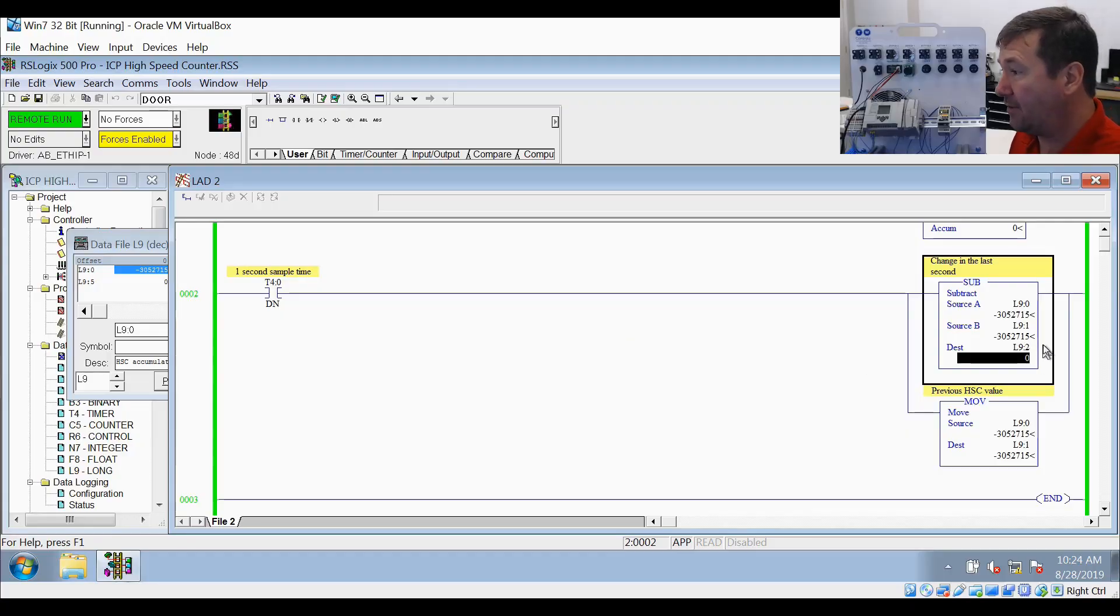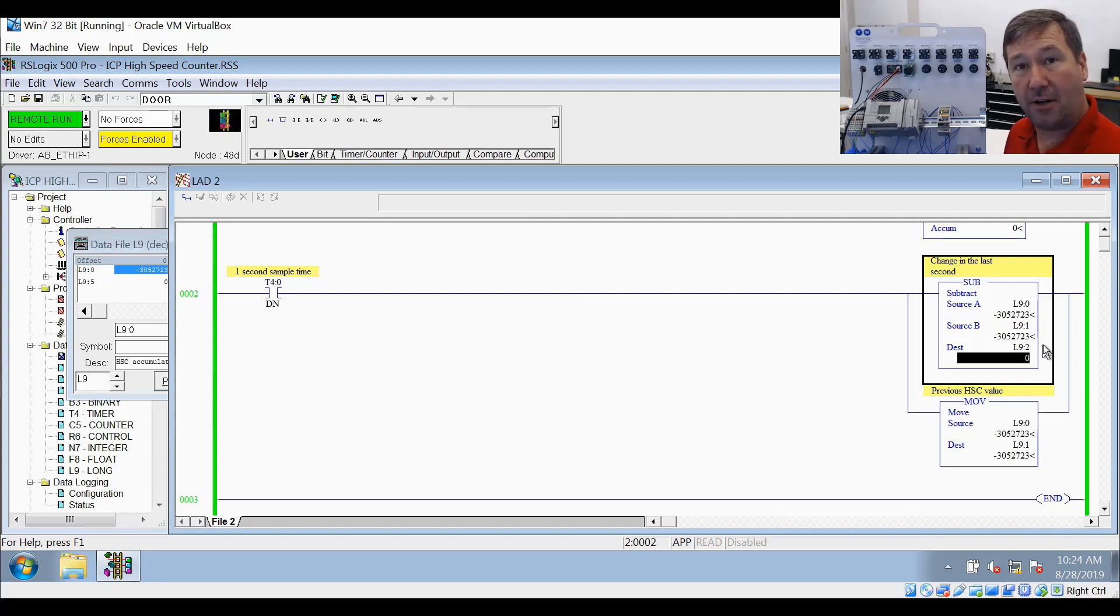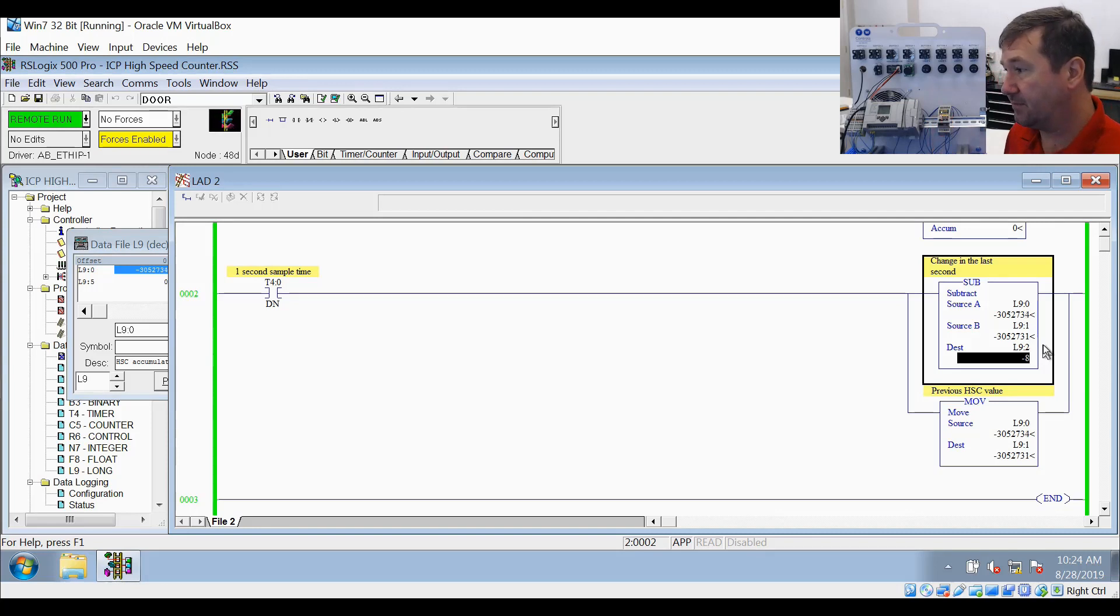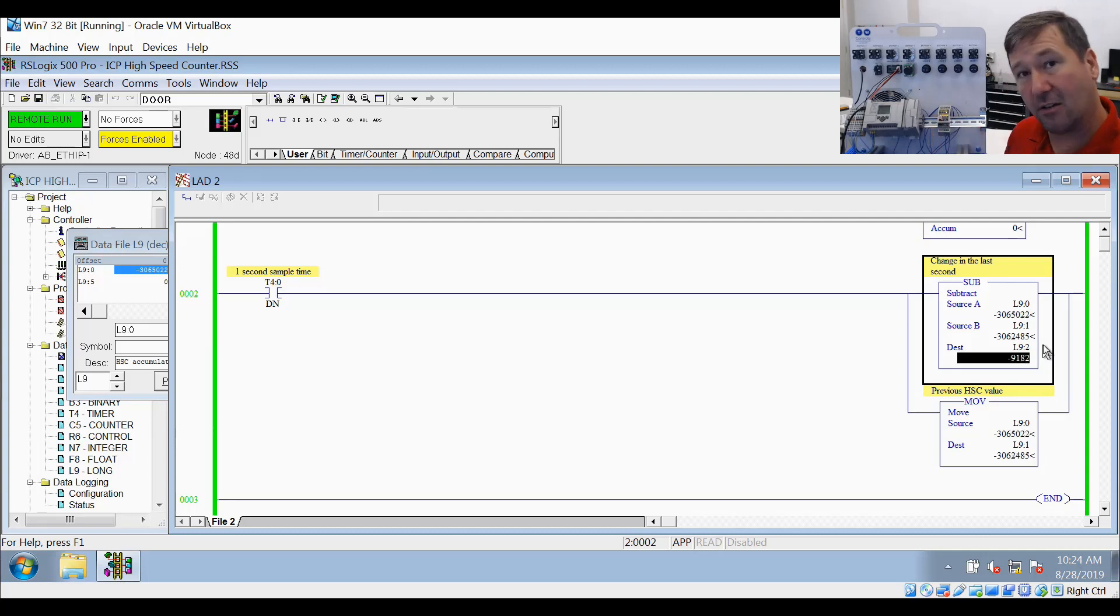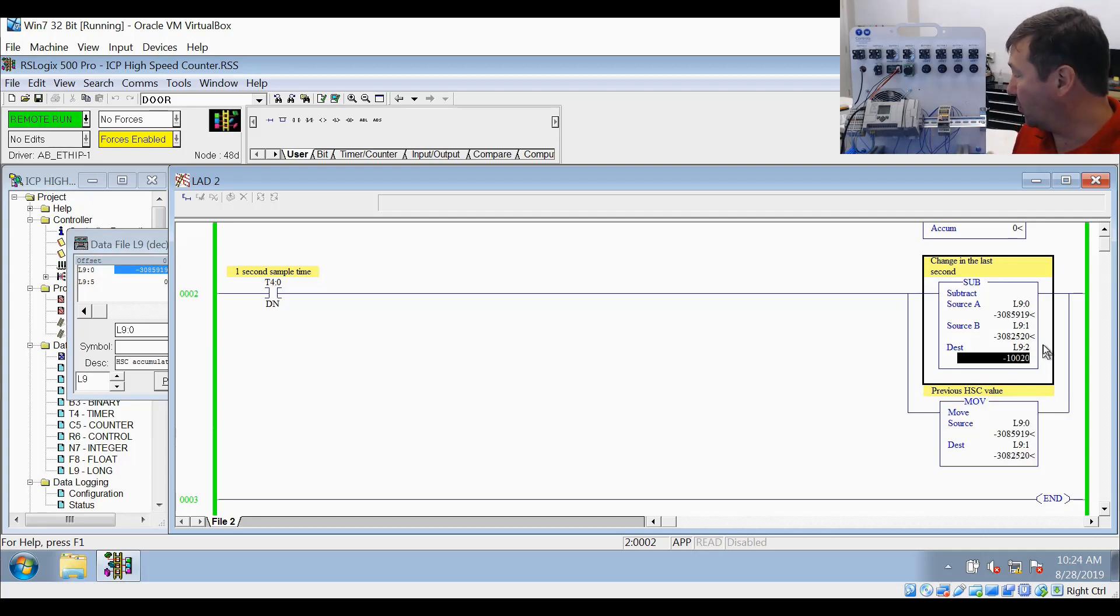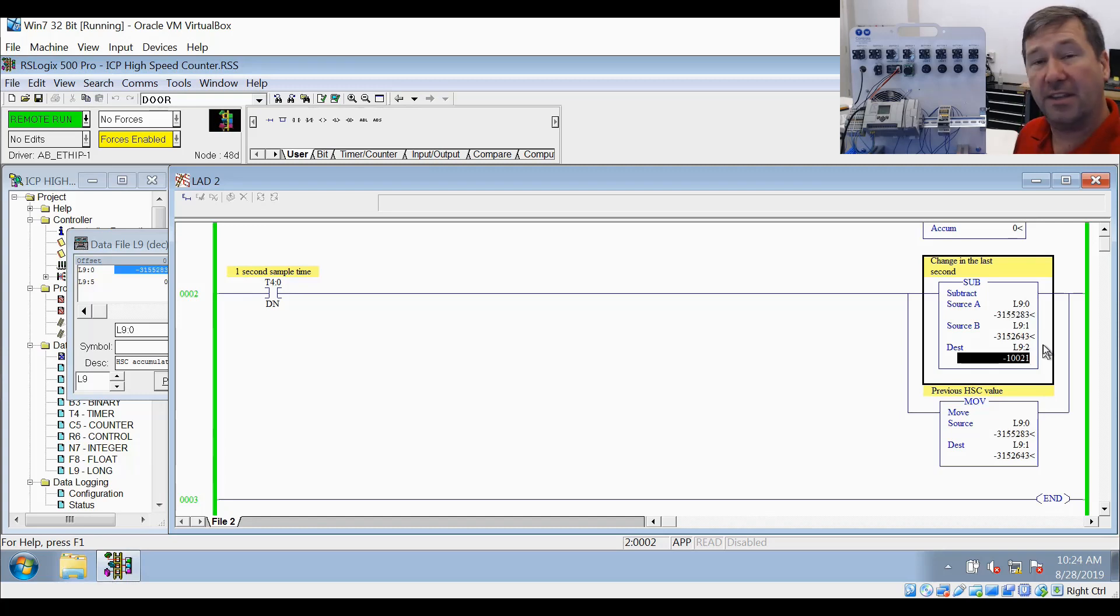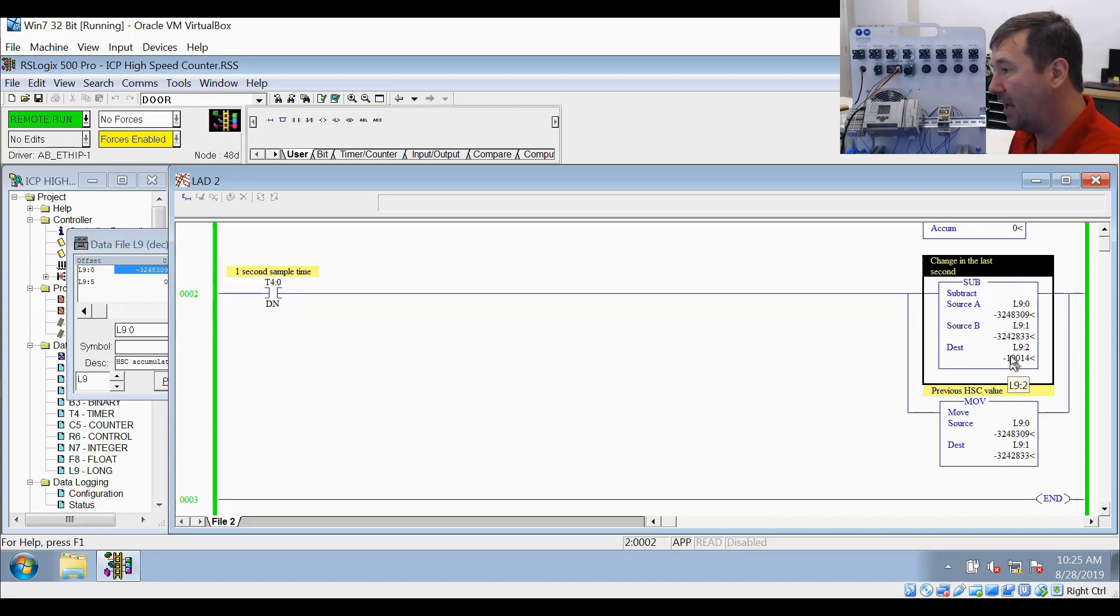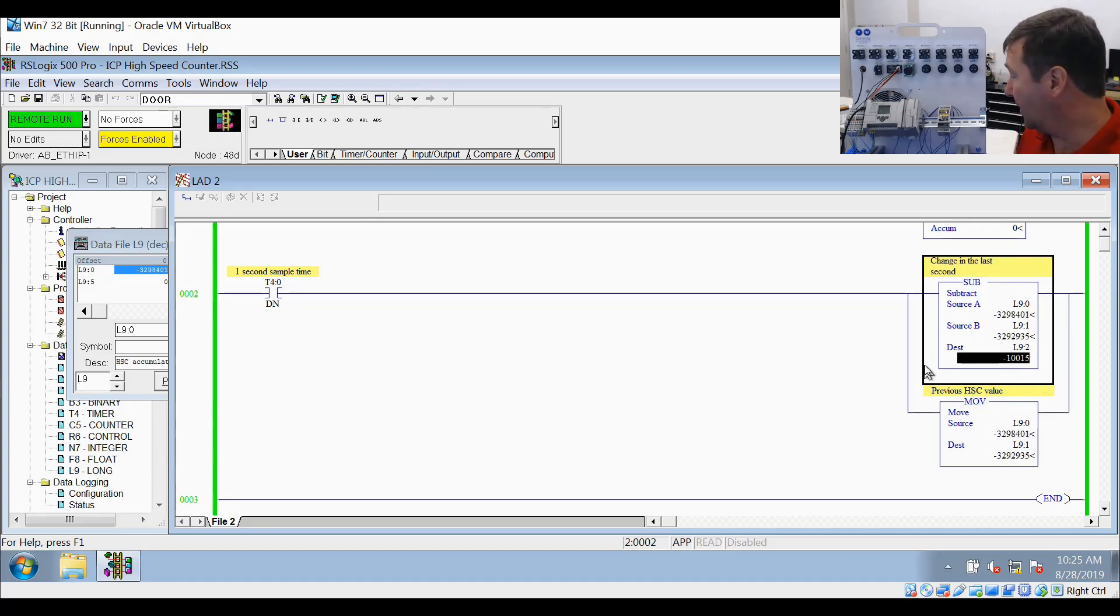I already have this program set up. I'm not going to go through how I configured this - I have a video on it and I'll put a link in the description. We have our encoder simulator wired up. If we hit our direction button, the encoder starts changing directions. We can change our frequency up to 10 kilohertz. Between 10 hertz and 10 kilohertz, we're going to see a difference in how the MicroLogix operates when these input filters are set wrong. This is from a previous video. We already have a rate set up here, and right now we're going roughly 10,000 hertz, which is exactly what it should be doing.